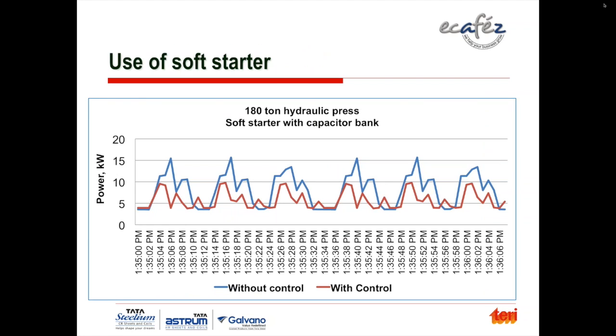The first example here: there are two ways of saving energy in these kind of motor-driven systems. One is using a soft starter with a capacitor, and the second would be a VFD. I'll give both the examples from that. Now, use of soft starter.